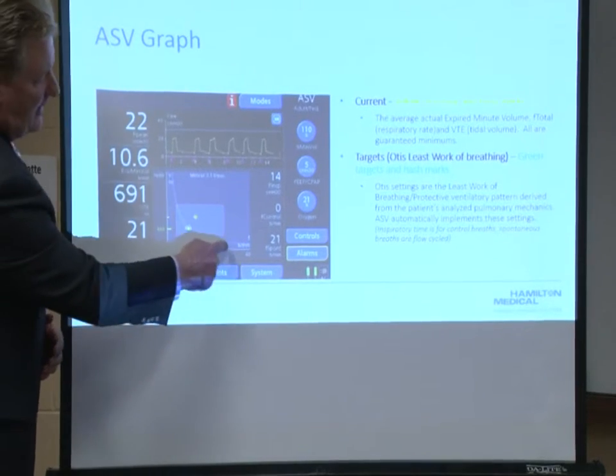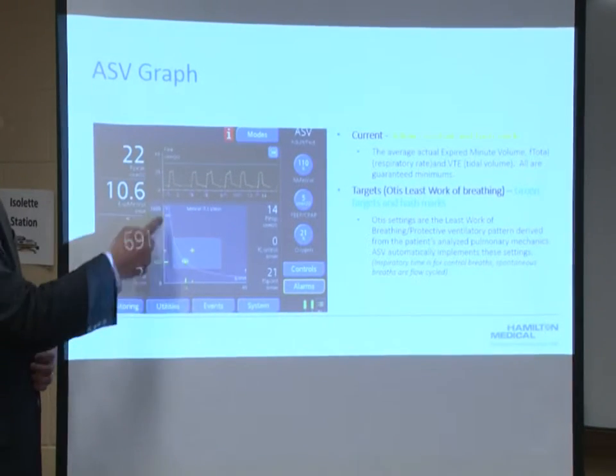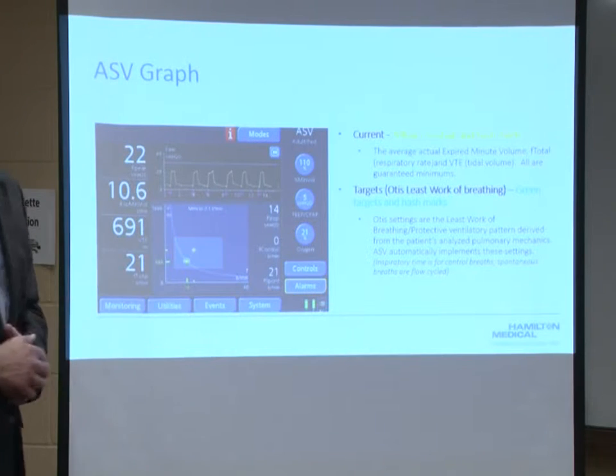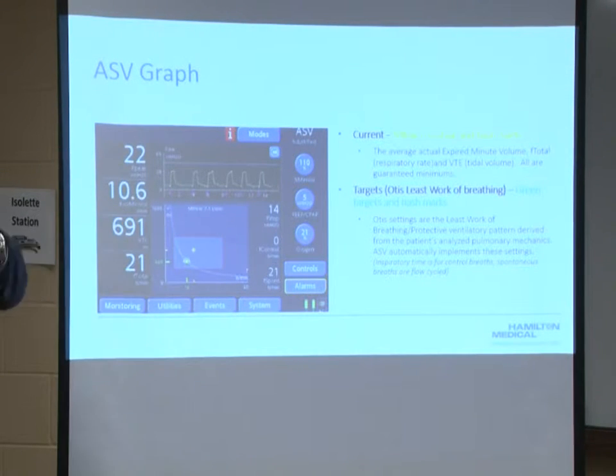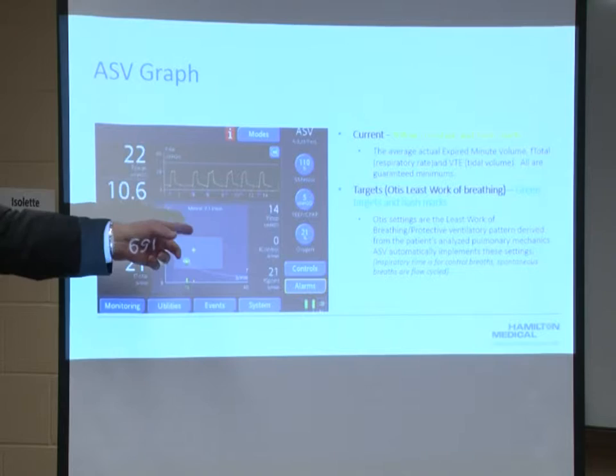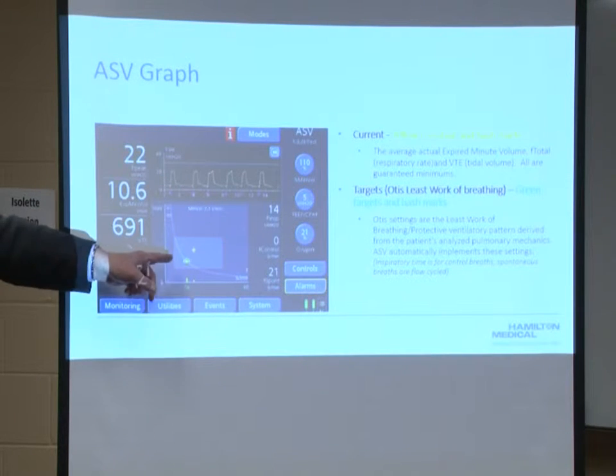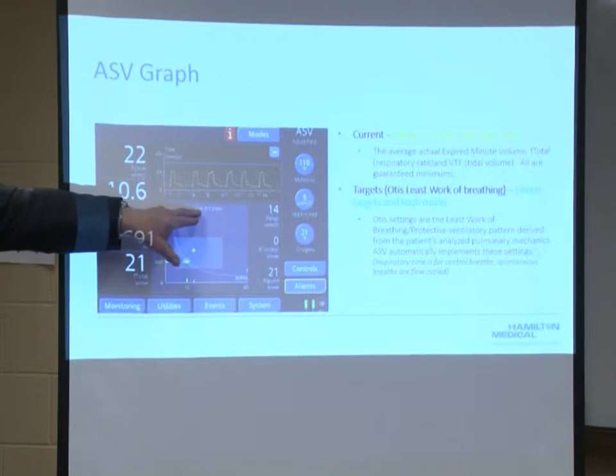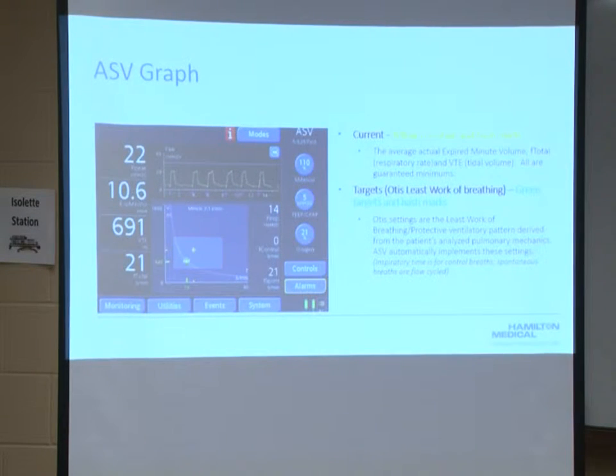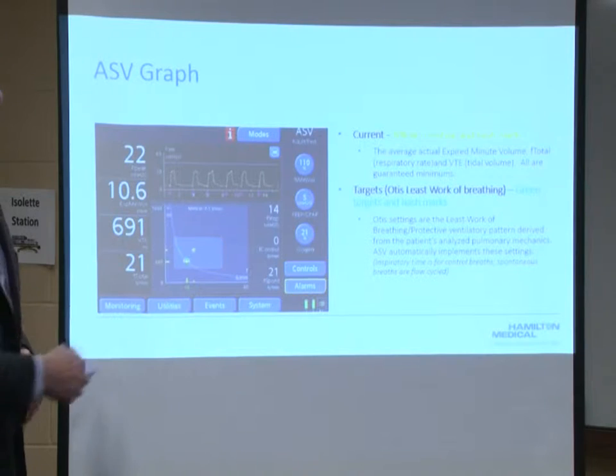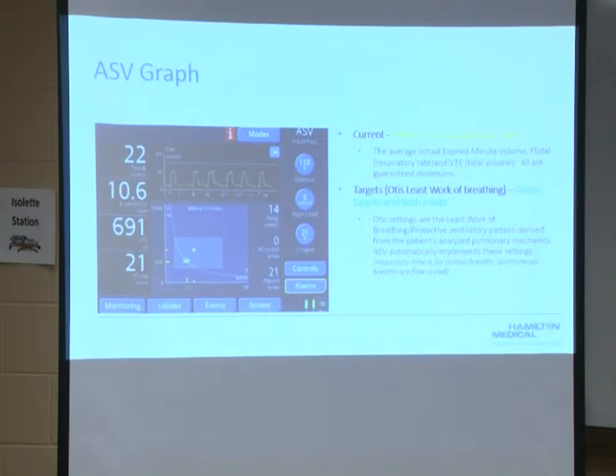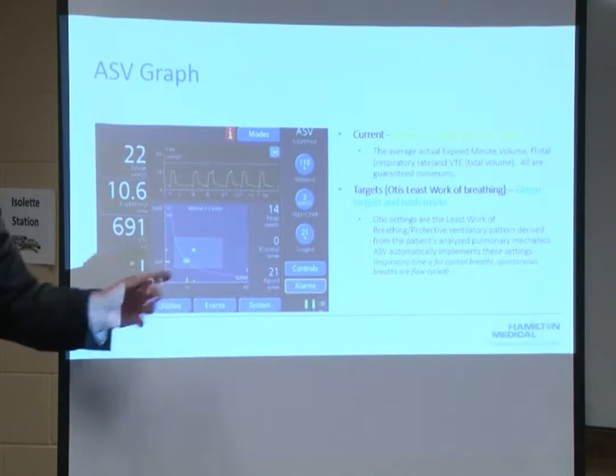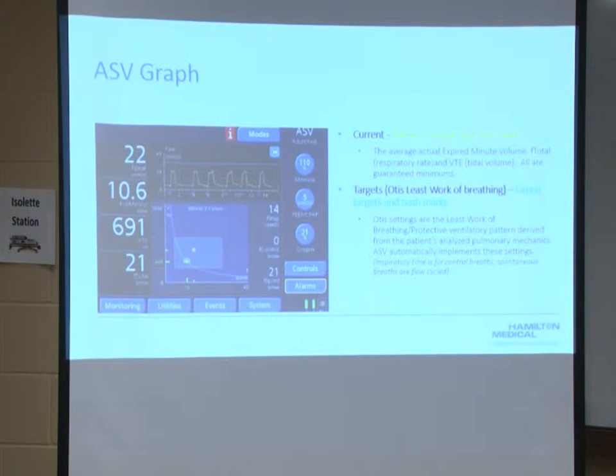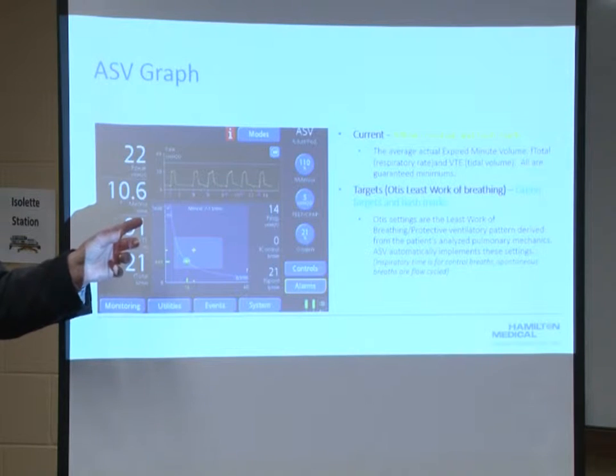And this curved line represents all the combinations of tidal volume and rate that will produce this. This is not your ventilators or mine, but when I was building the slides, I happened to have it on a different patient size. All of the combinations of tidal volume and rate that will produce that 7.1 liter minute volume. And the safety frame, the red box, think of the area inside the box as safe combinations of rate and tidal volume to use on that patient with that patient's pulmonary mechanics.